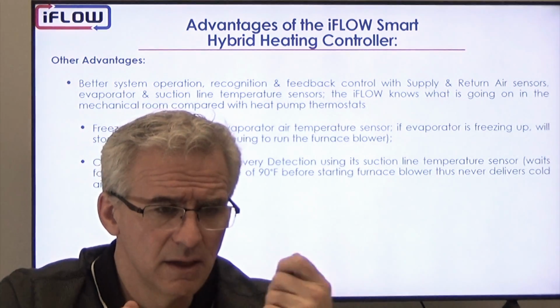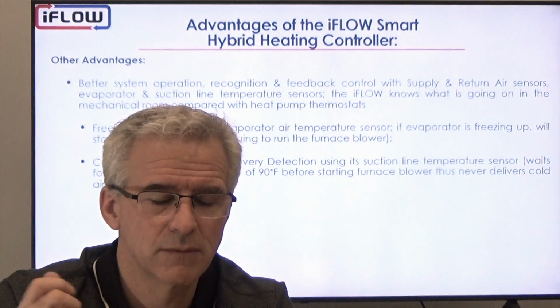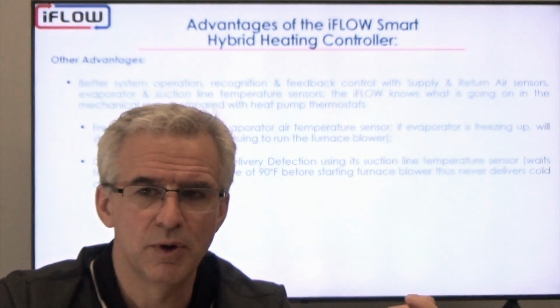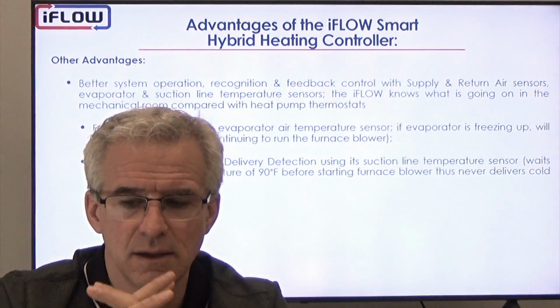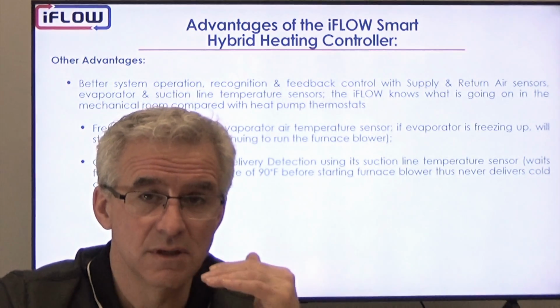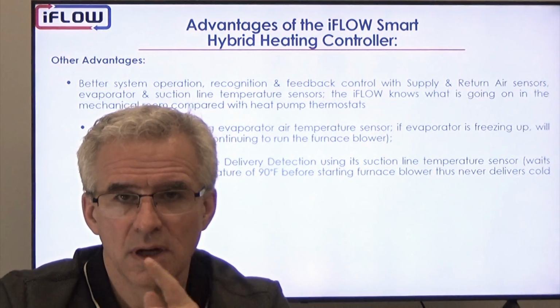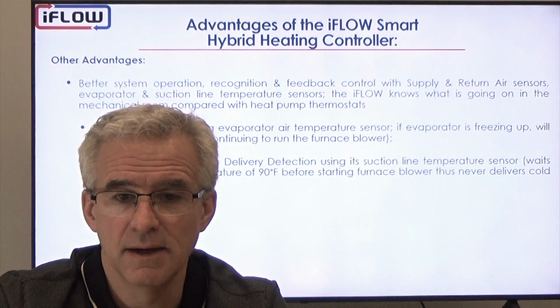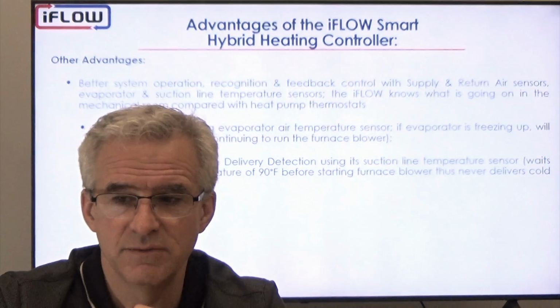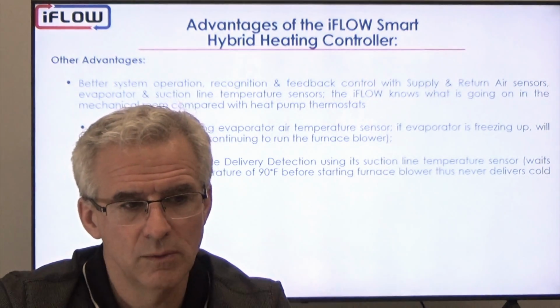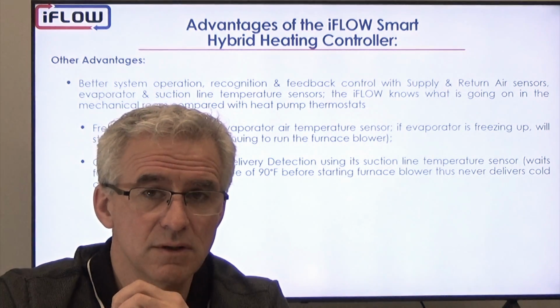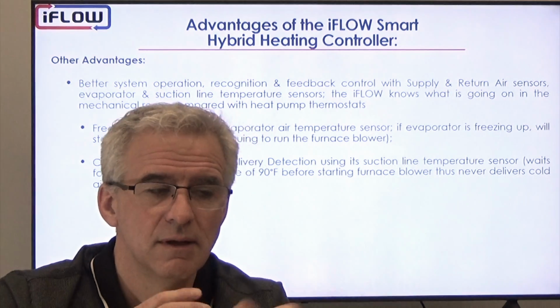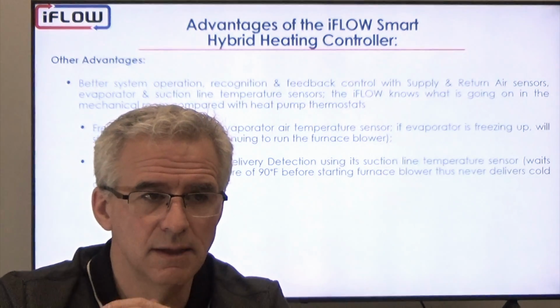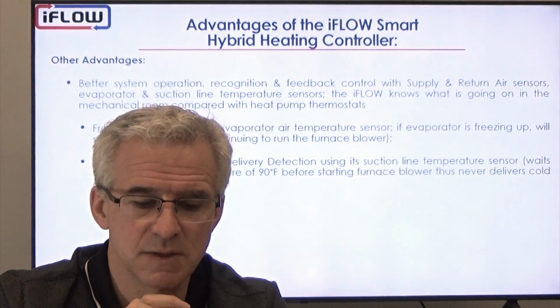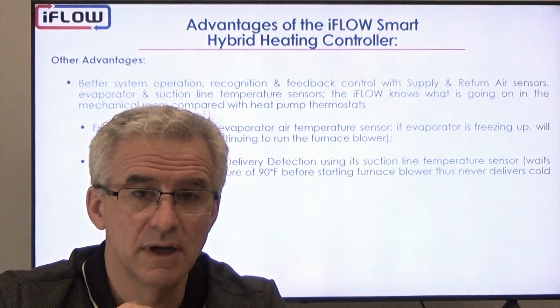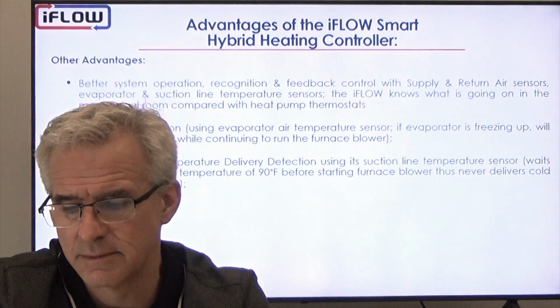If on a startup call for heat, we call on the heat pump and within 20 minutes we're not getting the temperature we need from the outdoor unit, if it's not gone above 90 degrees, then we will automatically switch over to the gas furnace and basically assume that the heat pump is having some difficulty. We will run it for that cycle. We will let the thermostat satisfy based on the gas furnace. Then we will switch back and we'll try the heat pump again. And if the heat pump continues not to be able to meet, we'll always switch over to the gas backup, ensuring that the home is never out of heat, that the heat load is always being met.